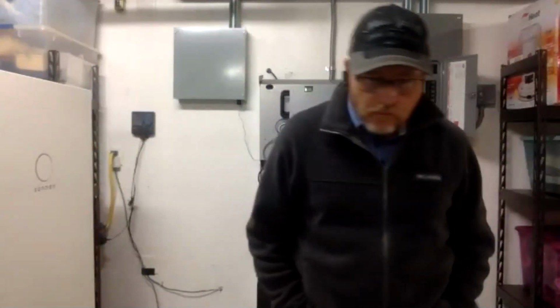Yes, there's a lot of surge that people don't account for. We have a 35 amp surge rating for 100 milliseconds. You multiply that by 240 and that gives you the kilowatt requirement, and people don't account for that.